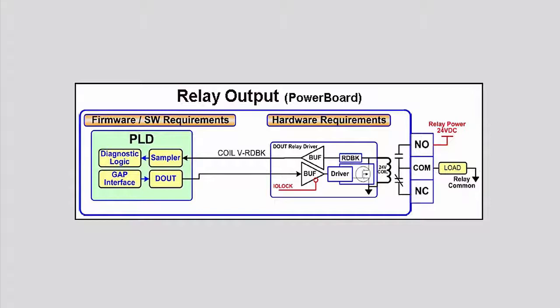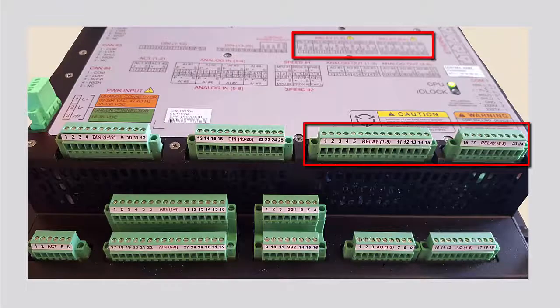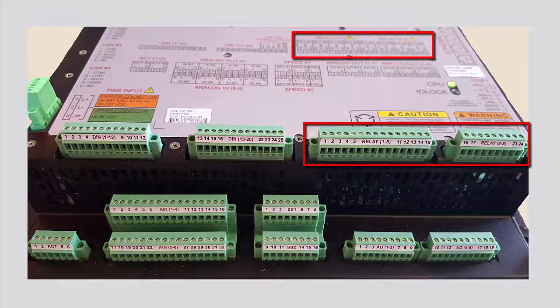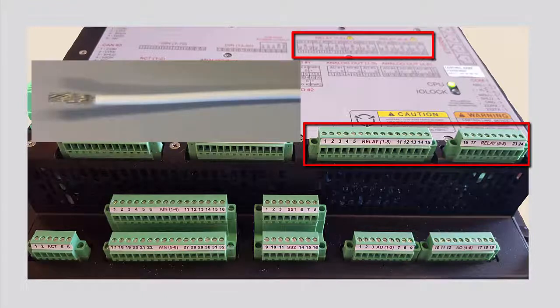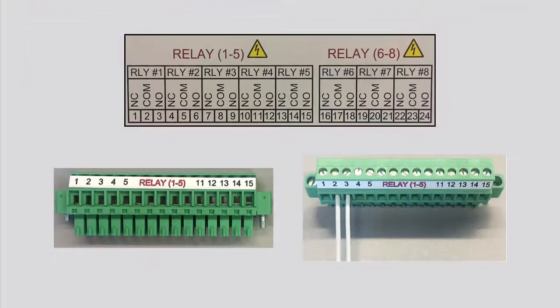Discrete or relay outputs on the controller are isolated and use form C relay outputs with normally open NO, normally closed NC, and common COM contacts. Each individual relay is separated into a numbered block containing the contact labels and corresponding terminal block numbers. To wire a relay output, use a 16 gauge wire.